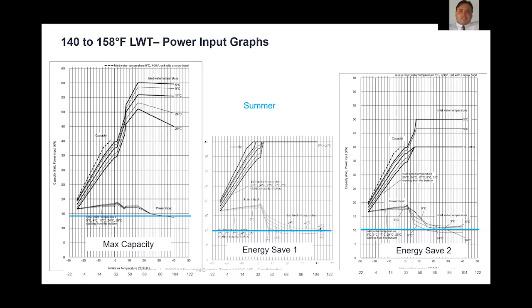And so again, if you have time of day rates where that's advantageous, if your building profile is such that you could take advantage of those higher recovery rates during the summer months, and that makes sense, you have options to do that, or to curtail those peak demands until off-peak hours, and do load up strategies to store hotter water temperatures in the morning, if that makes sense based on your specific utility rate structure, and then demand limit during those peak hours in the afternoon, which is probably more common with most utilities.